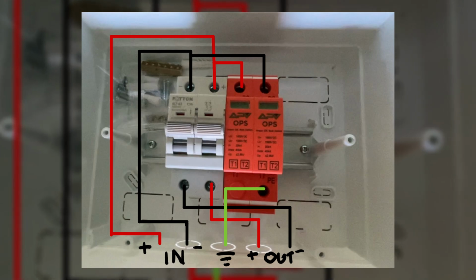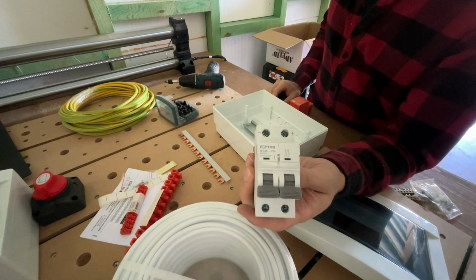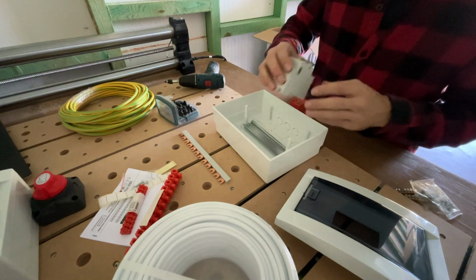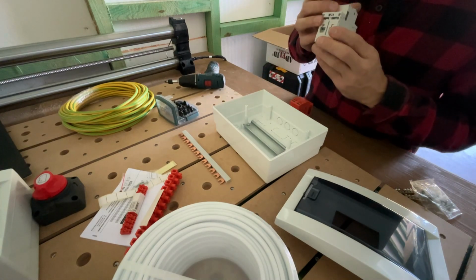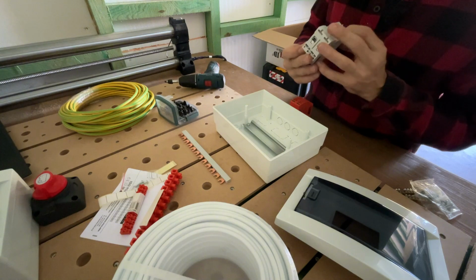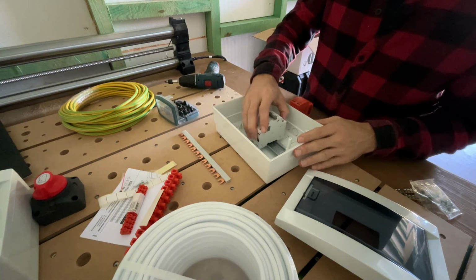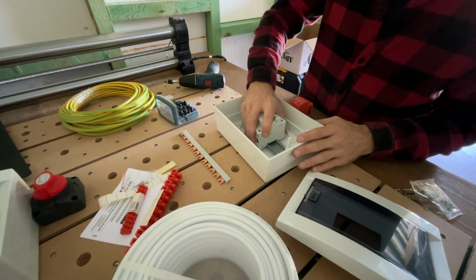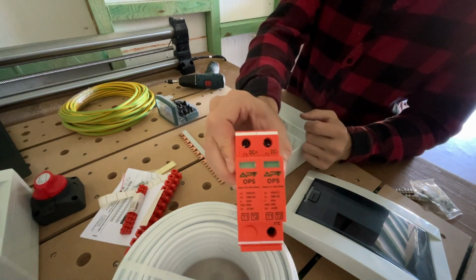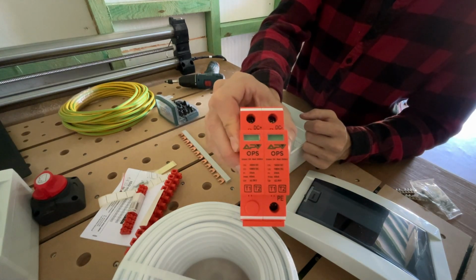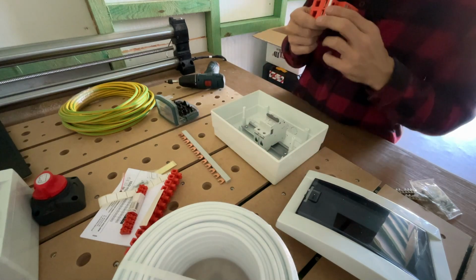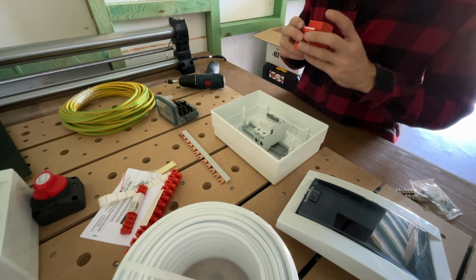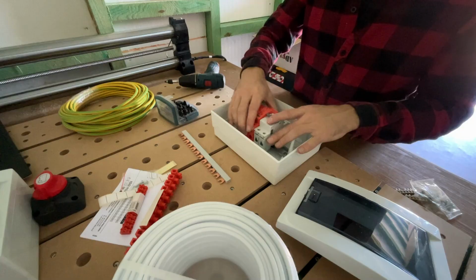I will use 2 components here. A DC circuit breaker for 500 volts and 16 amps. This is because my solar grid will operate in a range from 280 to 380 volts and will produce a maximum of 14 amps. The second component is an SPD for DC circuits. The principle of operation of this component is the same as in the AC circuit we did before. The last electric box is done.